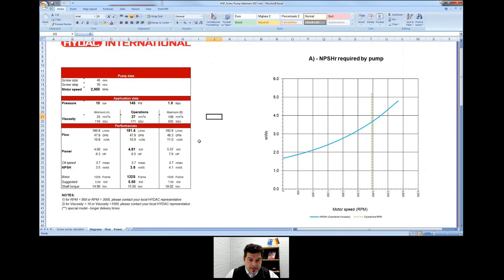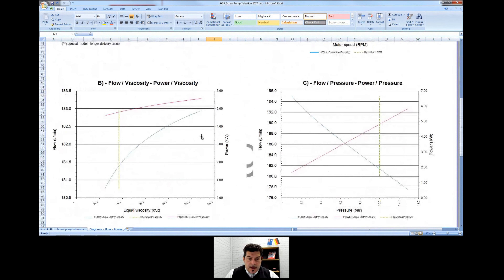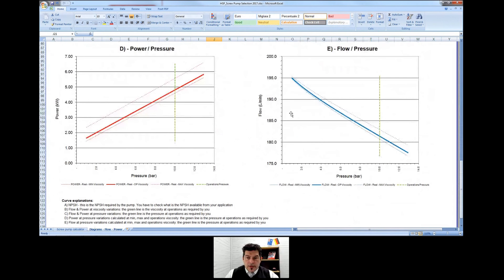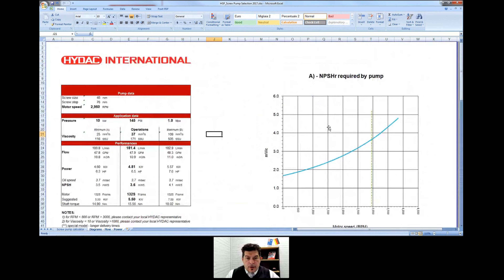We also give the customer charts showing how viscosity varies as a function of flow, how pressure changes as a function of flow, and the green line shows the working point of the pump as we have designed it. You also have pressure versus power and pressure versus flow, so with all these charts you can have the whole behavior of the pump in your installation — a given from HYDAC for every screw pump we offer.